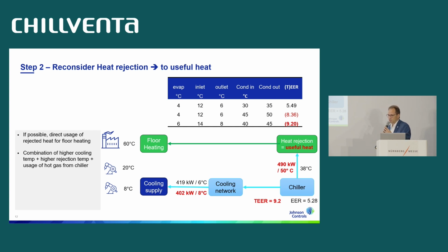So this is a chill pack running a typical cooling and condensation temperature of 38 degrees Celsius, giving you a very nice energy efficiency ratio of 5, serving a cooling network of 6 degrees Celsius and a capacity of roughly 420 kilowatt. By changing the temperatures of the condensation up to 50, the electrical energy efficiency ratio from the chiller drops, for sure. But then you are able to use 490 kilowatt as useful heat for floor heating.